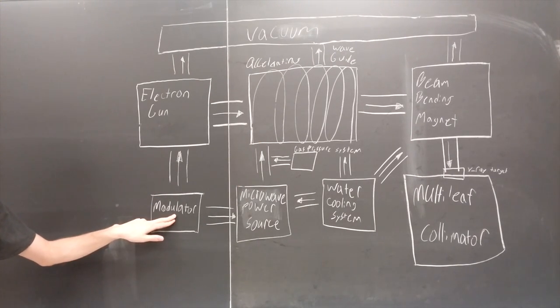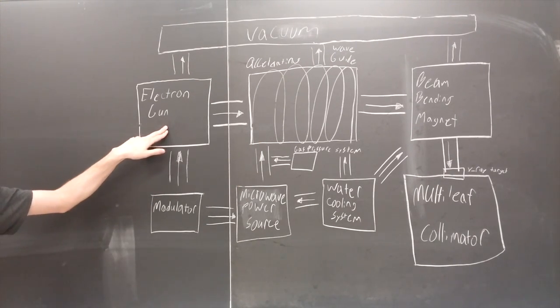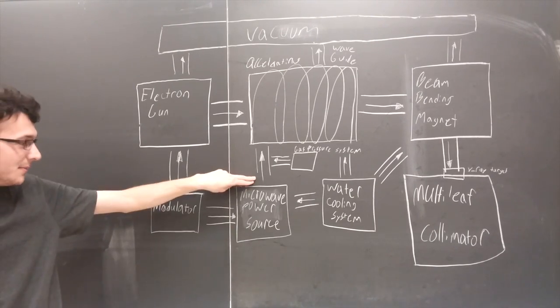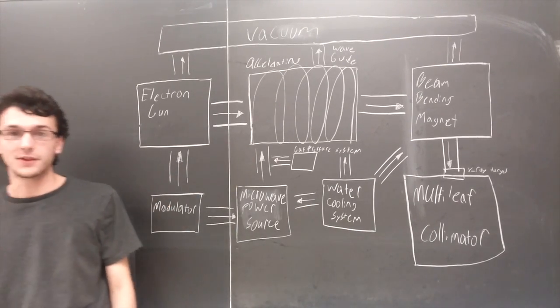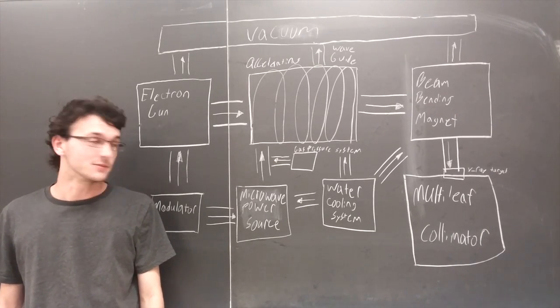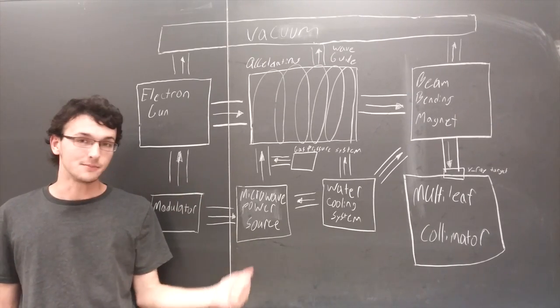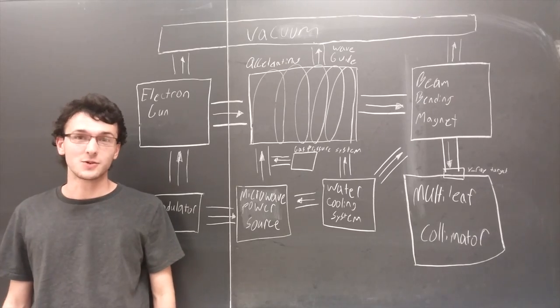Here we have the modulator, which regulates the amount of energy produced by both the electron gun and the microwave power source. It is important to note that we are able to exchange the mediums within the system. That will become important in the equations portion later.